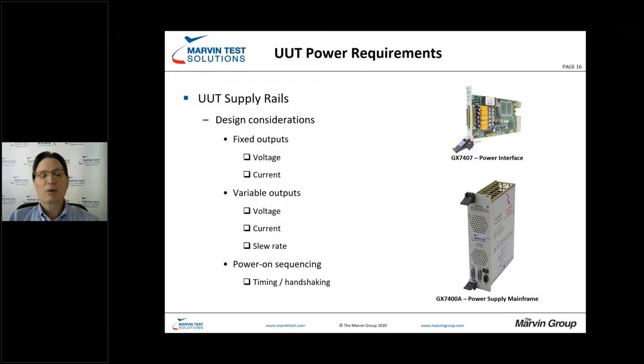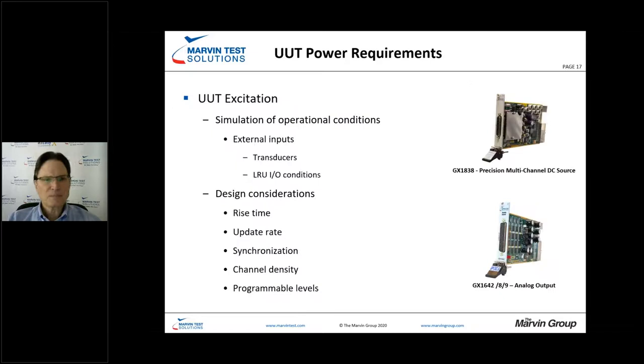From a power-on sequencing standpoint, we don't just apply power to our UUT and hope everything goes right. There are often very well-defined power-up sequences we must follow — apply this rail first, then the second rail, before applying any type of excitation to the unit under test itself.